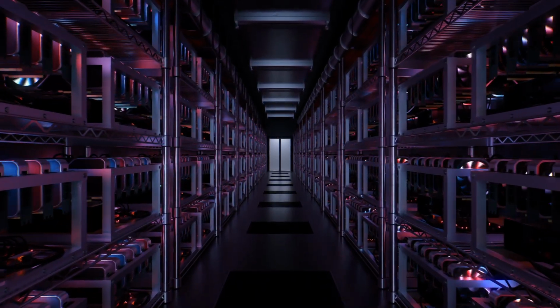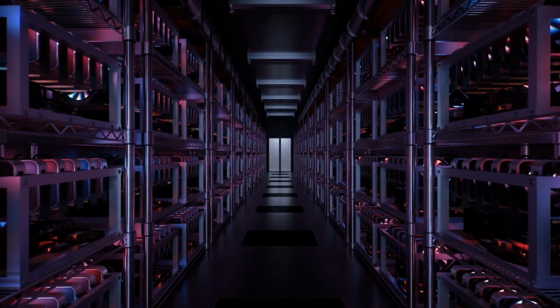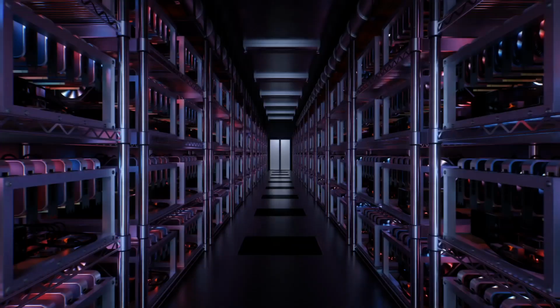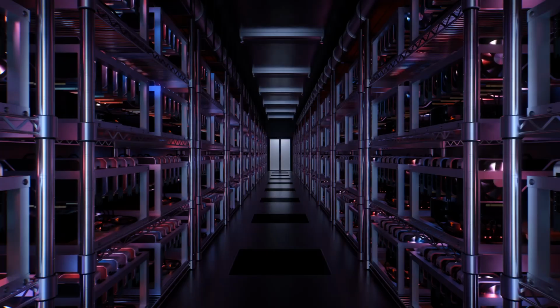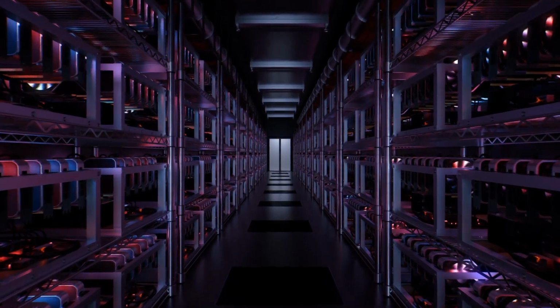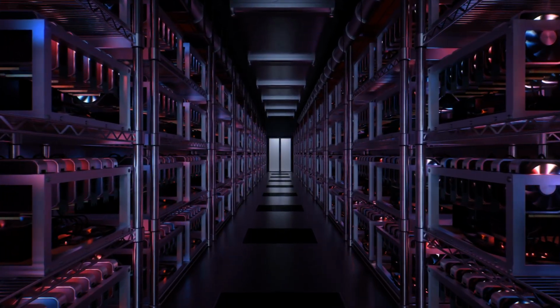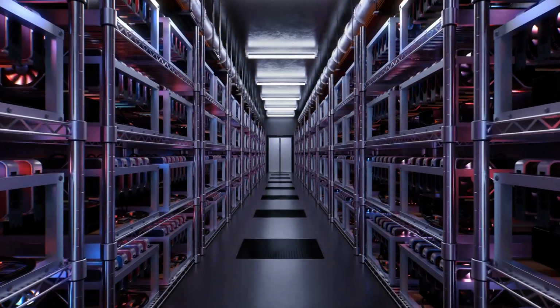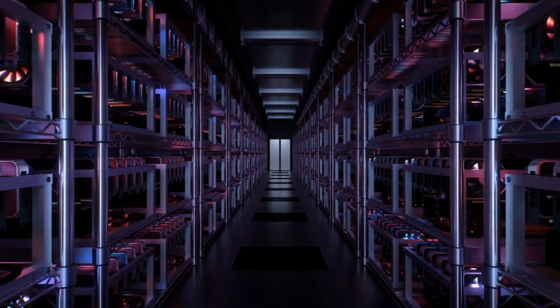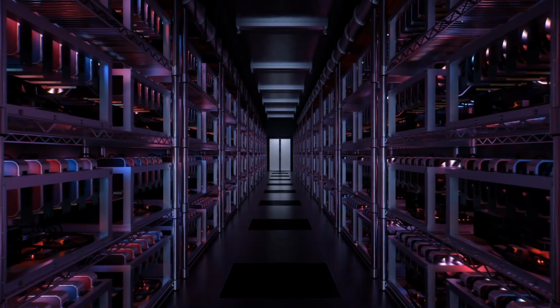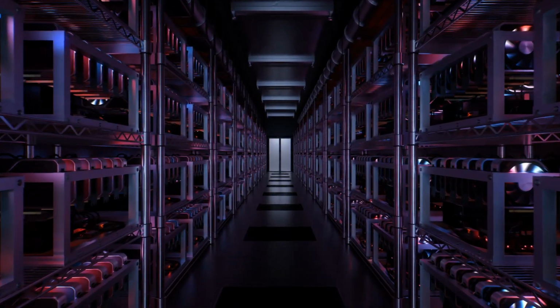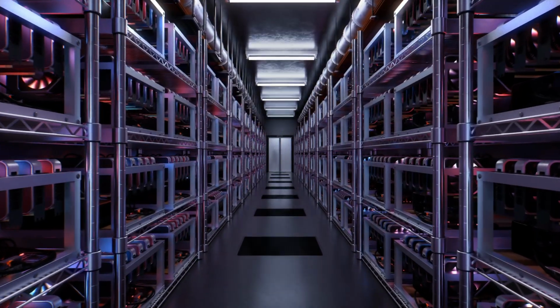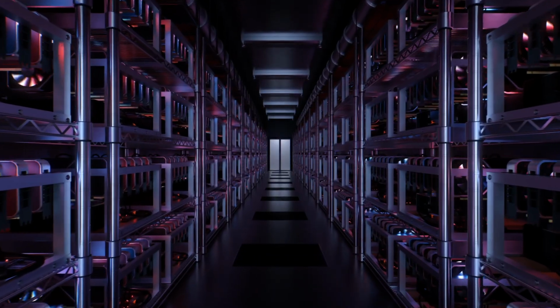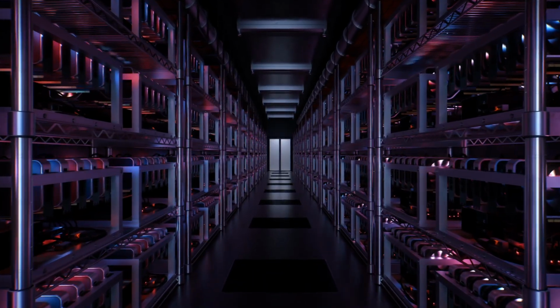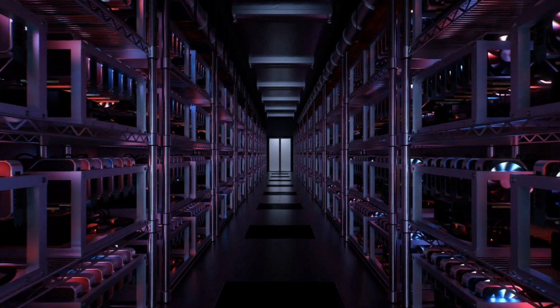And when data centers consume power on the scale of small cities, a drop in PUE from 1.8 down to 1.2 translates directly to massive reductions in carbon emissions, especially if that local grid is powered by fossil fuels. It makes the entire operation exponentially greener, absolutely, but it also makes it significantly more cost-effective. The single highest ongoing operational expense for any data center is not the hardware itself, it is the electricity bill. Right. Lowering the PUE fundamentally changes the profit margins of the facility.